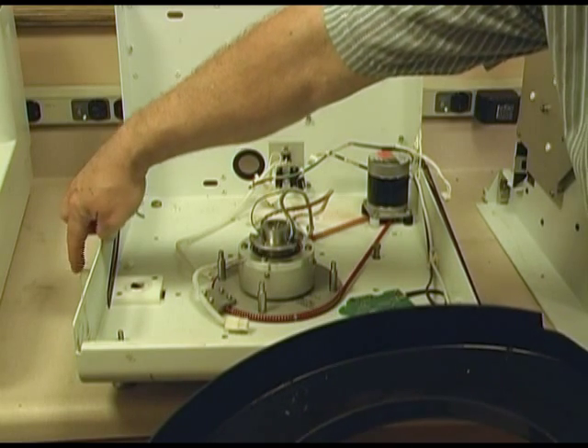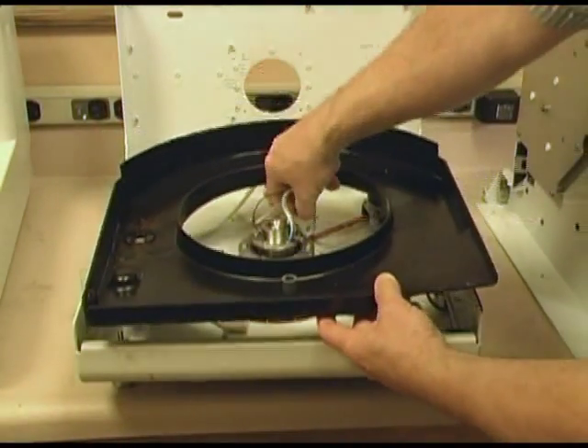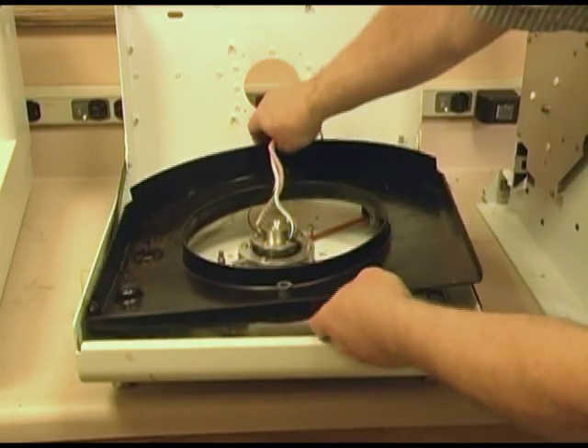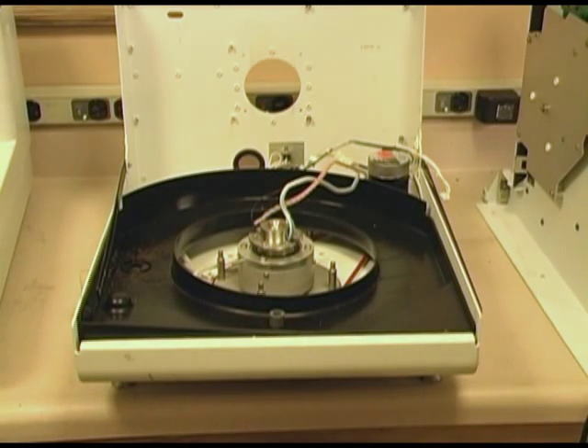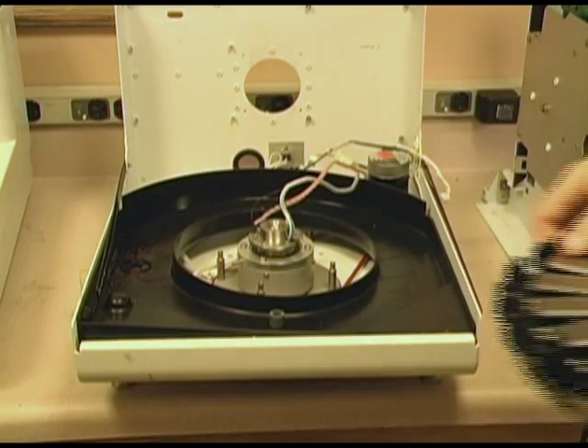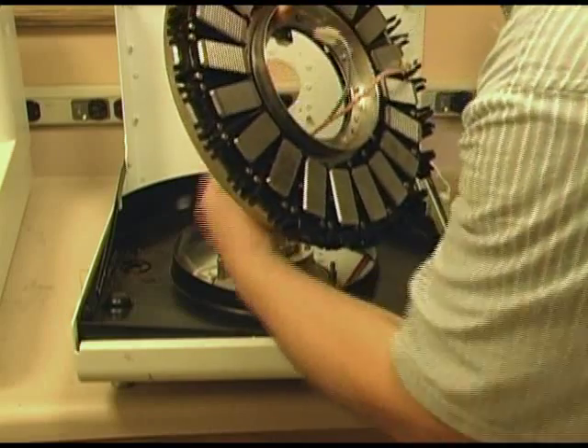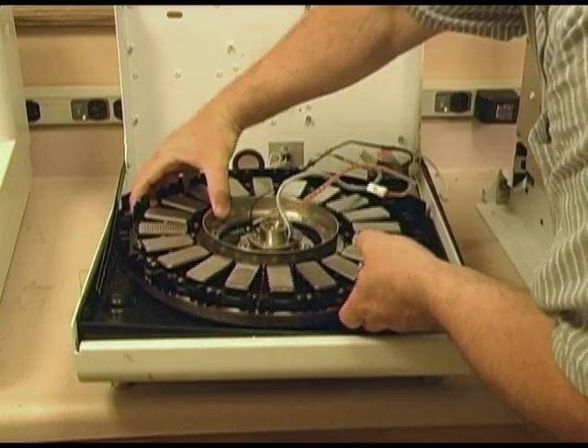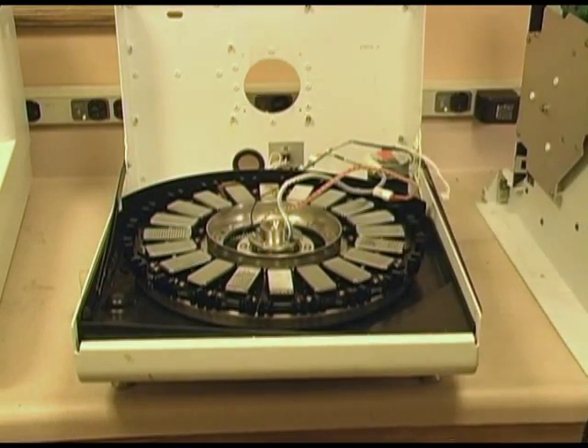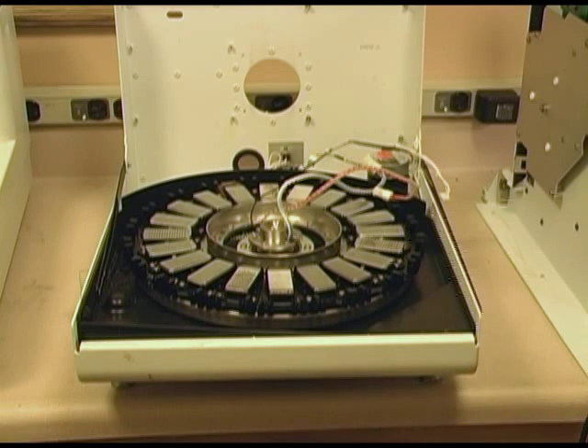For preventive maintenance, that drain needs to be cleaned out because it clogs up once in a while. This goes on top of here, and on top of that goes the carousel. It's very easy to take this off — not a very complicated unit as far as that goes. It goes on and off fairly easy — essentially four big screws — and that's what you have. That bottom chain drives the slides around.